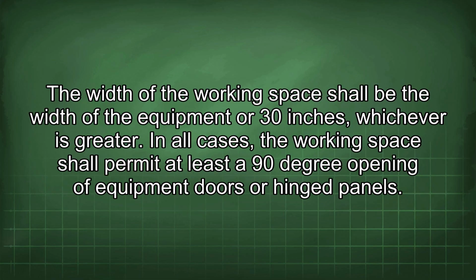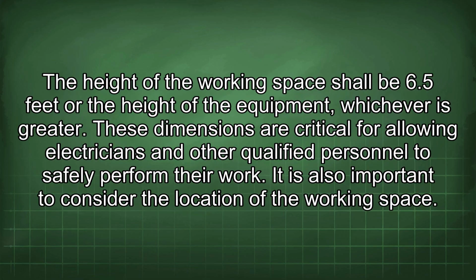The width of the working space shall be the width of the equipment, or 30 inches, whichever is greater. In all cases, the working space shall permit at least a 90-degree opening of equipment doors or hinged panels. The height of the working space shall be 6.5 feet, or the height of the equipment, whichever is greater. These dimensions are critical for allowing electricians and other qualified personnel to safely perform their work.